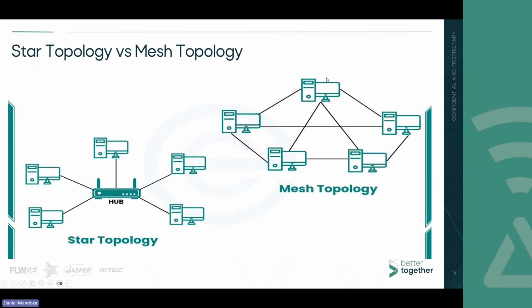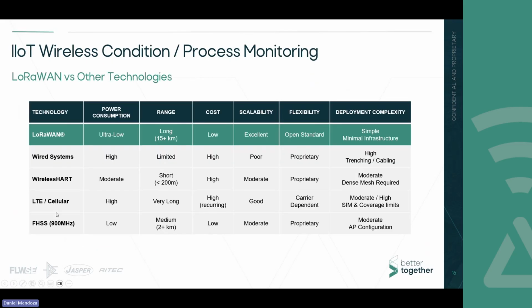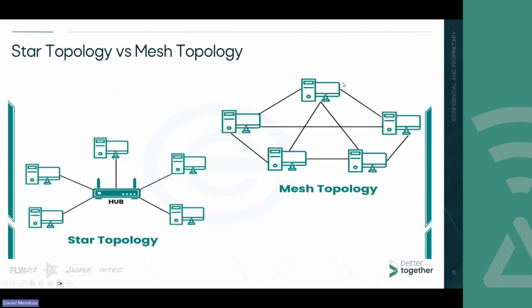Mesh has its place when it comes to process control, but for something where I'm using preventative maintenance with sensors, just gathering data and not controlling a process, I don't need all this redundancy. With that redundancy, you're going to have shorter ranges and higher costs to operate, because I'm going to need 18 to 20 gateways to communicate, since you're creating a redundant network. If my point fails here, I want it to be able to go here, and that's going to require another gateway to repeat that signal.